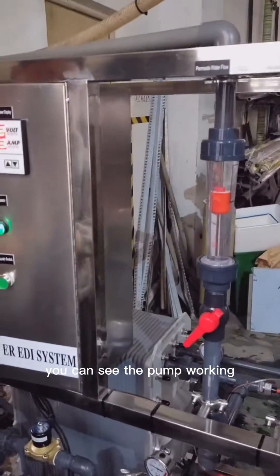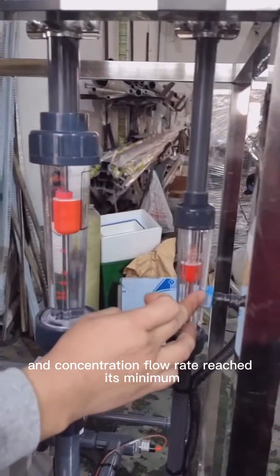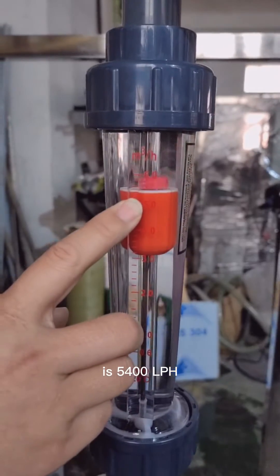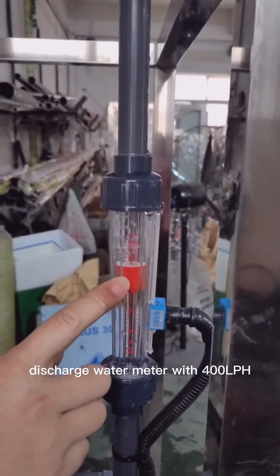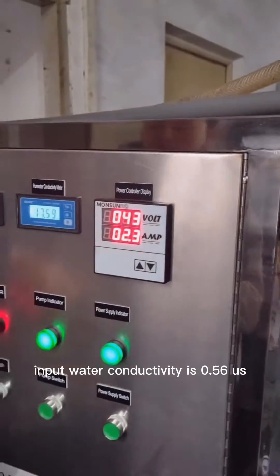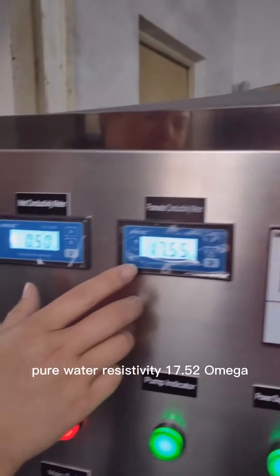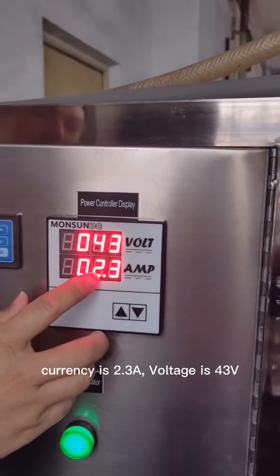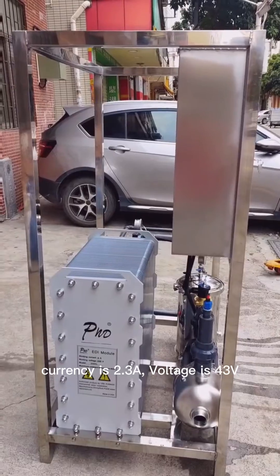You can see the pump working, and the concentration flow rate reaches its minimum. The permeate flow rate is 1,400 liters per hour, and the discharge water rate is 400 liters per hour. Input water conductivity is 0.56 µS/cm. Pure water resistivity is 7.5 MΩ. Current is 2.3 Amps and voltage is 43 Volts.